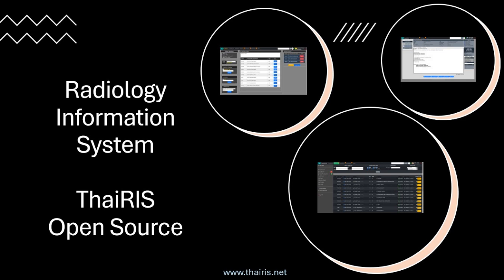What are some highlights there? Yeah, these are really about optimizing things for bigger, more complex places. Things like auto printing to external devices, deeper HL7 integration, specifically mentioning setup help with Mirth Connect, and supporting MPPS messages.